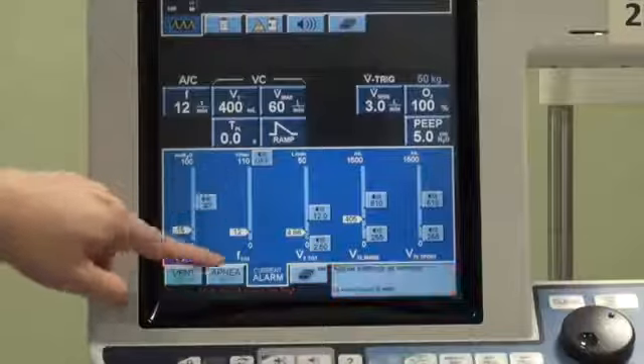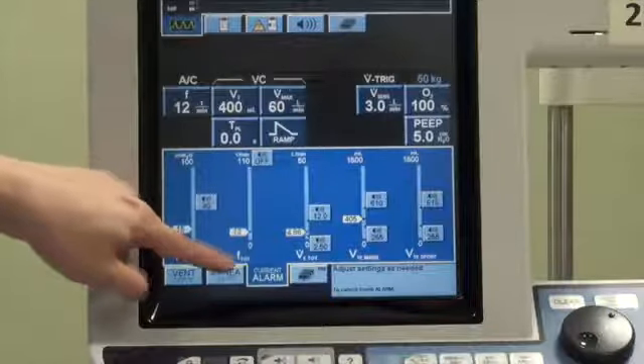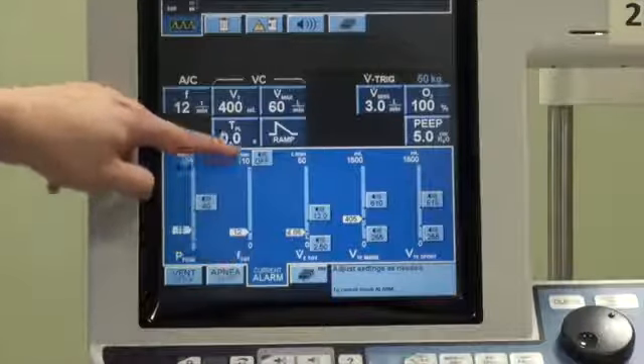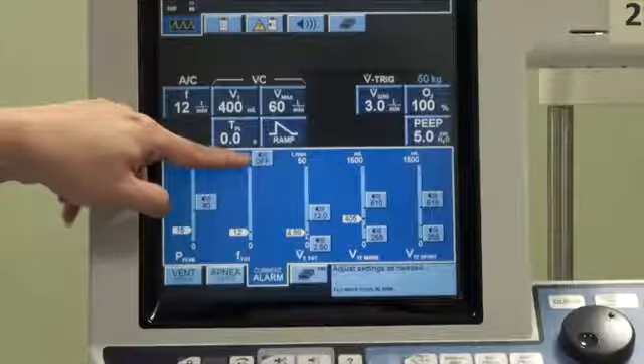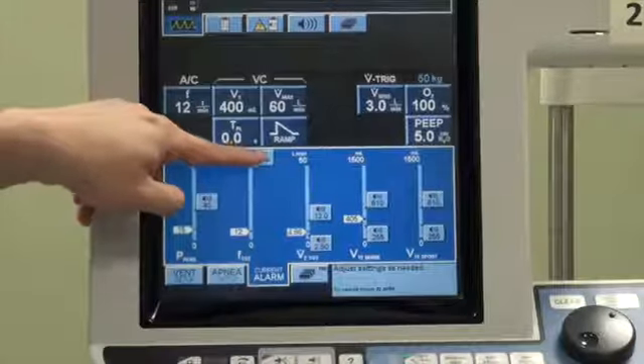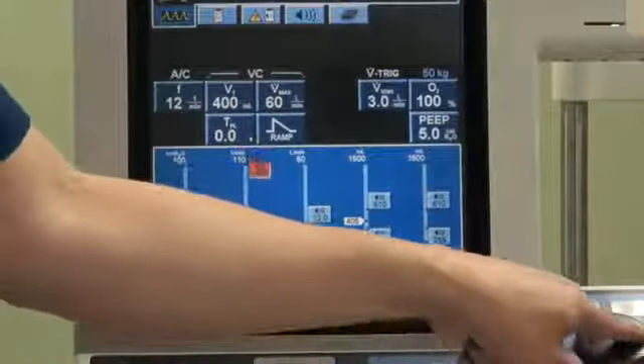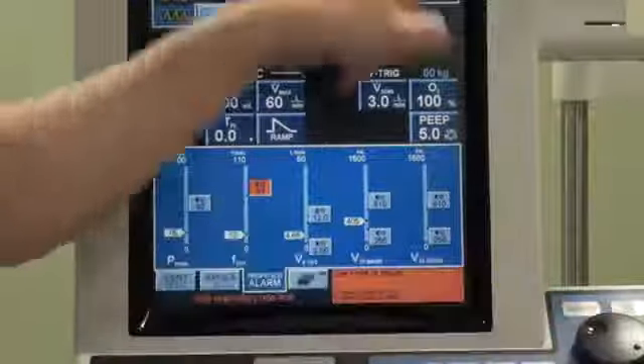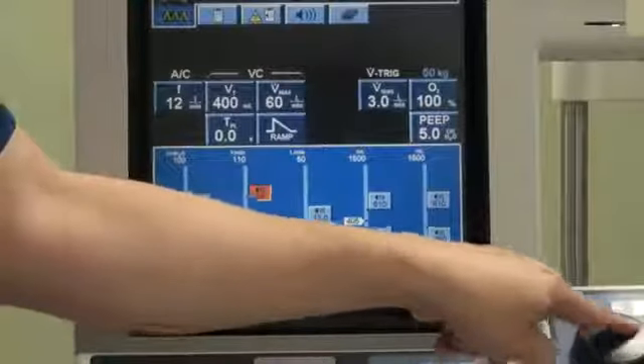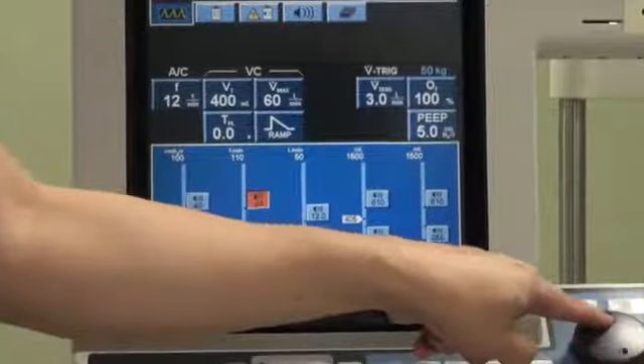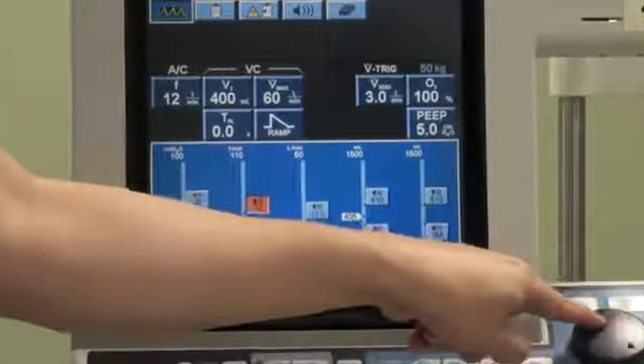All right. The second button is actually for the frequency. By default, the upper limit of frequency is put at 100. But obviously, you want to be alerted when the patient is breathing beyond a certain limit. And for this particular patient, the resting frequency is around 12. So I may want to set it around, let's say, 20. And the machine will alert me when the breath goes beyond that.